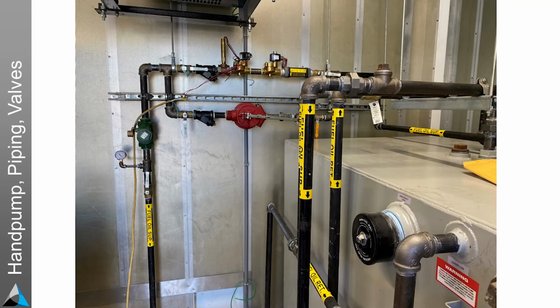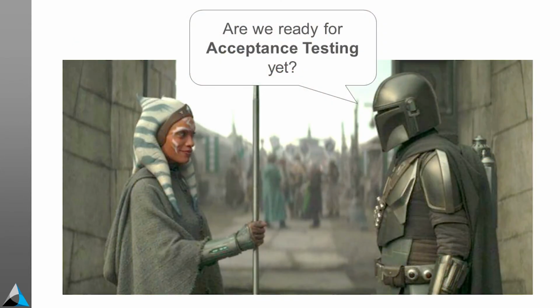There's the hand pumps, and when they went to test them before we showed up, bless their hearts, they actually went to test the system. They broke the hand pump, which means it was a little hard to pull fuel, and then they replaced it, and we tested it, and it ended up working. But I'm looking for these labels—again, I'm a big fan of labeling and directional arrows and all that. If I can figure it out, then somebody else can figure it out.